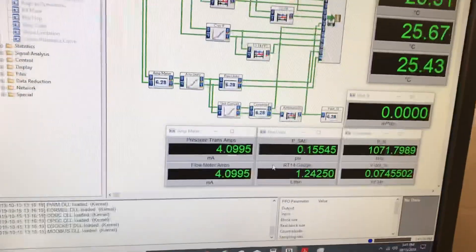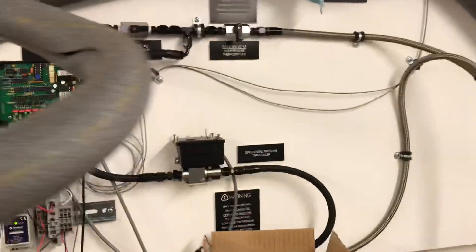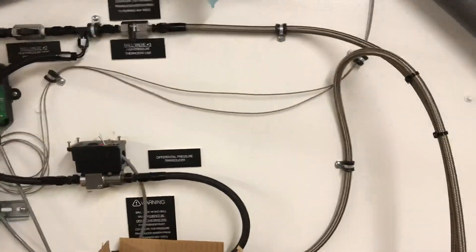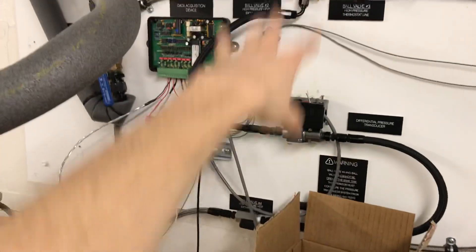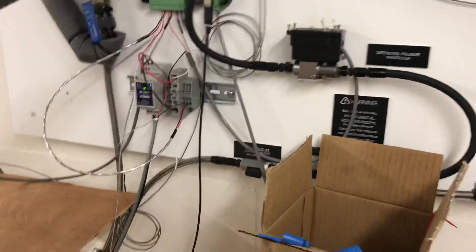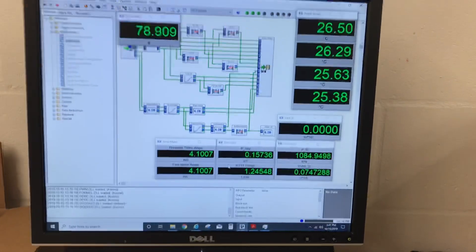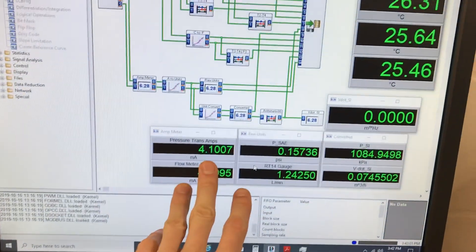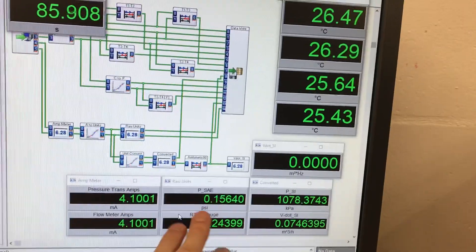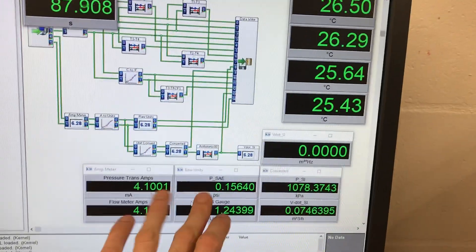Unfortunately it seems like I'm going to have to change my scaling, or go into the utility again to change some of the stuff in there. What I was going to try to do first — then I realized, because this system was not set up by me, we already are going to have an issue getting this to be perfect, just because we've got this high aspect always pushing down on a pressure transducer. Not my design, thought about it way after the fact. So it's hard to make sure I can get a real reading of zero.